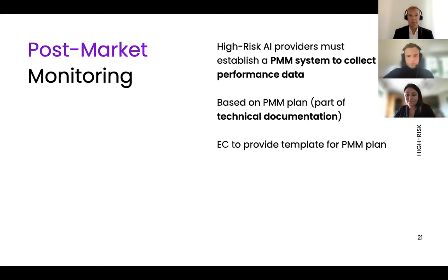The post-market monitoring system must be described in a post-market monitoring plan that is a mandatory part of the technical documentation. And as a supportive measure, the European Commission has promised to provide a template for these post-market monitoring plans. That's not there yet, but it will help manufacturers in drawing up this piece of the technical documentation.